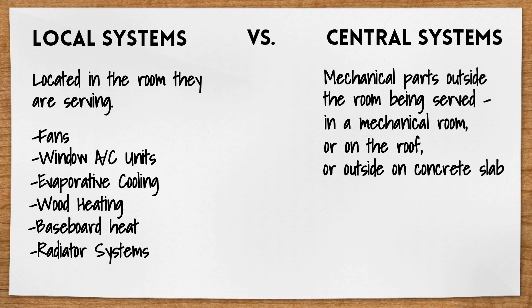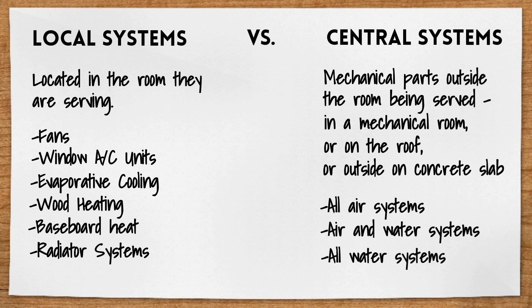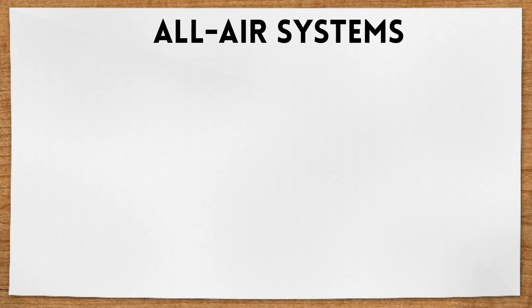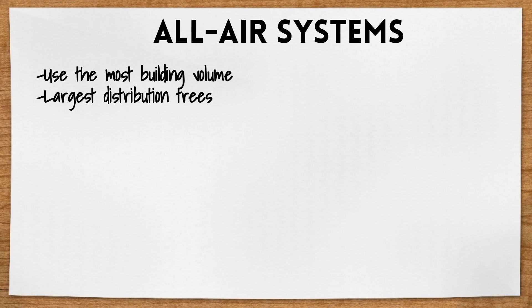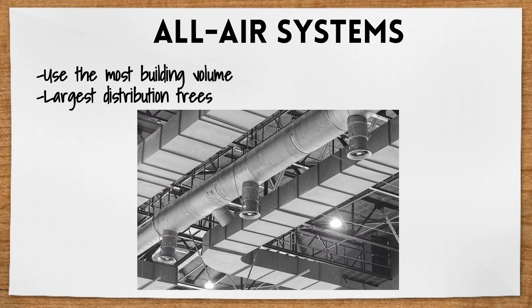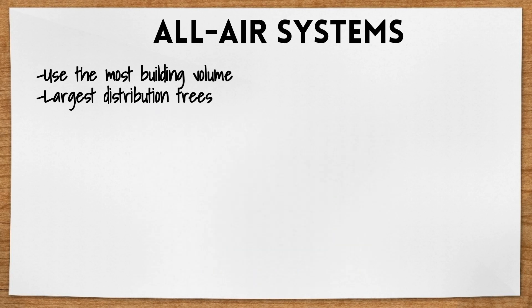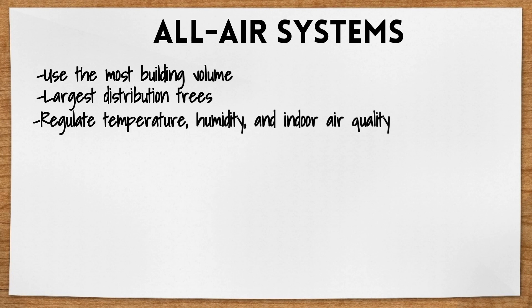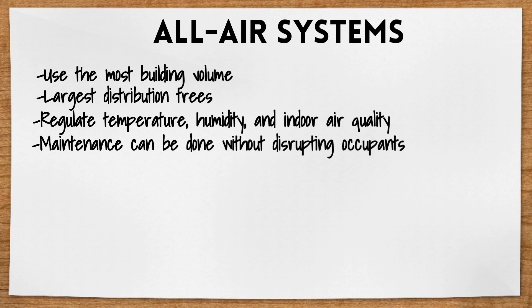Central systems can be split up into all air systems, air and water systems, and all water systems. All air systems use the most building volume since they require the largest distribution trees — those sheet metal ducts that usually look like this. However, they do give the best results by regulating both temperature and humidity as well as indoor air quality. They typically concentrate all their mechanical equipment in the central mechanical room so that maintenance can be done without disrupting the building occupants.